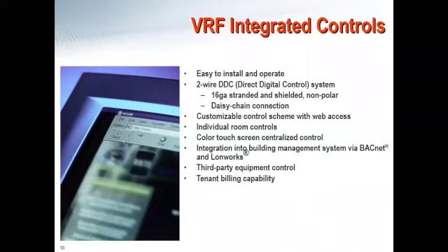One thing I will say without getting too manufacturer-centric is that VRF technology is capable of completing all of these. So if you have an application where you're looking to tie into a BMS, or integrate the VRF system with a bunch of third-party equipment, that is not going to be an issue. Also, tenant billing is something VRF is very good at accomplishing. A lot of manufacturers on the market have the ability to go into a tenant billing application. It's really good if you're serving a bunch of individual apartments. Most VRF manufacturers can break down energy usage by apartment and individually bill those tenants, typically with a third-party billing agency.